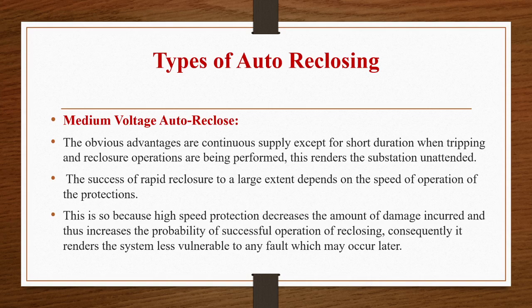Success of rapid reclosure to a large extent depends on the speed of operation of the protections. Why are we using this medium voltage auto reclose? Because whenever a tripping is done, the substation will be unattended if it is doing the work automatically. So success of rapid reclosure to a large extent depends on the speed of operation of the protections.